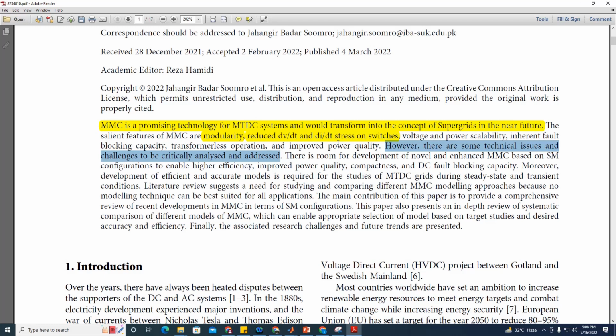If circulating current is not properly suppressed, this leads to the capacitor voltage ripple problem, because MMC consists of cells, and each cell has capacitors. The capacitor equation has a DC component, which is desired, but also a ripple component. If circulating current is not controlled, this ripple component increases, which is problematic and compromises power quality. So circulating current must be suppressed.